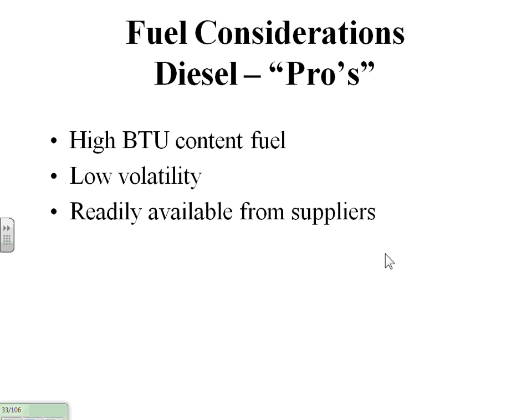Even in cold weather like Minnesota, North Dakota, these areas of the country, different refineries around the area, Koch refineries down in Coates, make additives that allow higher cetane ratings mainly for diesel systems, and it's kind of an anti-gelling agent as well. So there's a lot of additives that we put in to keep the trucks running and so on in the cold weather that we have, and our generators.